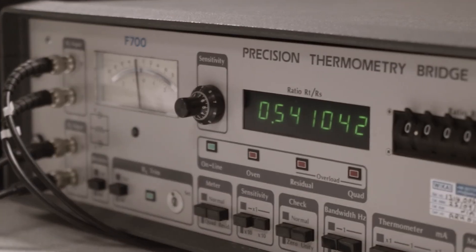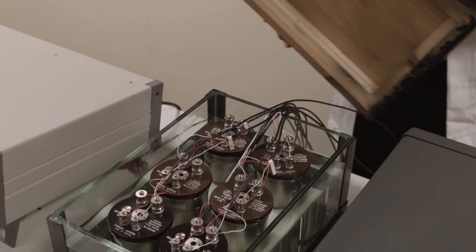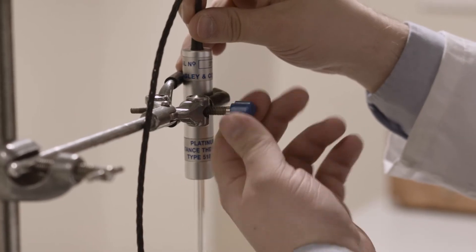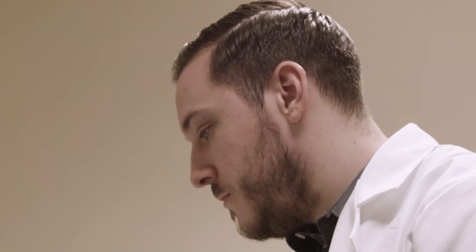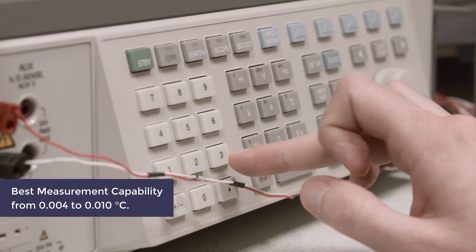Test measurements are made when testing and calibrating resistance thermometers using a range of laboratory AC and DC resistance bridges. These use Wilkins standard resistors as reference standards. For measurements made using this equipment from minus 200 up to and including 525 degrees Celsius, the best measurement capability granted by UKAS to the laboratory is between 4 and 10 thousandths of a degree Celsius.